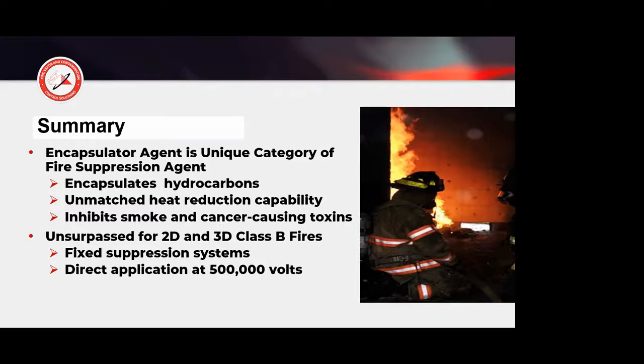By the way, after seeing how the agent worked, this gentleman, Anthony Natali, who's the head of emergency response for Con Edison, joined the NFPA 18A technical committee, and he has brought some of that testing, and that's been folded into the NFPA 18A testing, so that you would be able to now, once UL is geared up to do it, because currently they're not geared up to do it, you would be able to go and get your agent listed for electrical devices with certain standoff distances with the agent. Currently, the only Class C listing criteria available in the world is UL 711 for a fire extinguisher. And we're certainly not going to go out to a transformer fire with 20,000 fire extinguishers.